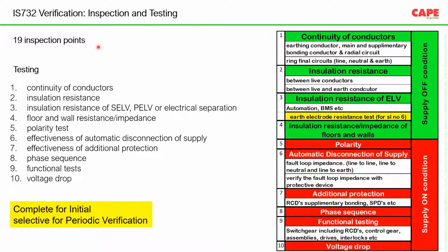Followed by that, there are 10 tests included in the standard. Now, here I have put continuity of conductor. Actually, in the future, I won't use continuity of conductor. If I put continuity of conductor, I'm sure an electrician will take a small tester and check the continuity. Actually, continuity of conductor is not continuity checking. It is the resistance measurement of a wire. The resistance of earthing conductor, main and supplementary bonding conductor, and the final live conductors in a ring circuit. All these three things shall be measured and compared with the data. So the standard gives you a maximum allowed resistance for a circuit, and we are supposed to measure it and ensure that the resistance is within that particular limit.